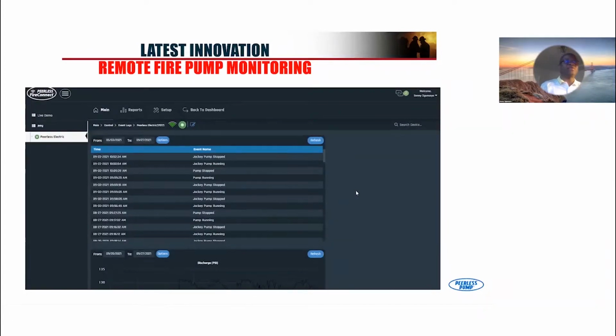You can also get additional information if you download some information, as far back as you want, 6 months, 7 months, a year, and it can tell you what's been going on in the fire pump room: when the jockey pump is starting, when it's stopping, when the actual pump is starting, when it stopped, or the frequency of the jockey pump starting and stopping and things like this. This basically tells you what's going on. If your jockey pump is starting very often, like 2-3 times every minute, that probably tells you that you have a leak in the system. So you really want to fix that before the problem gets bigger.